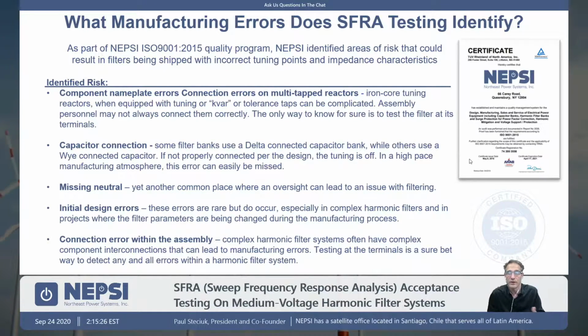So this is a slide that talks about it, and we developed this because of our ISO 9001 certification process. We are looking for ways to identify manufacturing errors in harmonic filters. Historically, what most manufacturers do is measure the capacitance, or look at the capacitance test reports from the supplier of the capacitor bank. They look at the test reports from the reactor supplier. They look at the nameplate. They put it into some type of Excel spreadsheet, perhaps the NEPSI spreadsheet. They put in those values and they get a frequency scan.